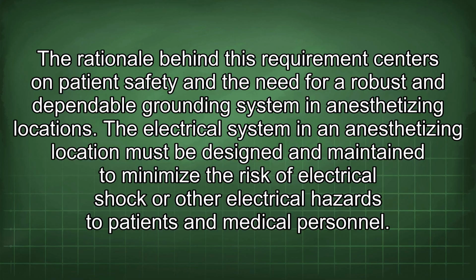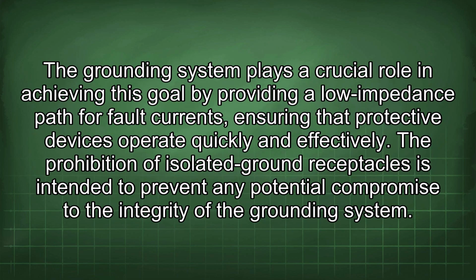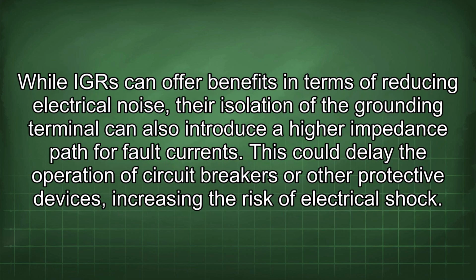The electrical system in an anesthetizing location must be designed and maintained to minimize the risk of electrical shock or other electrical hazards to patients and medical personnel. The grounding system plays a crucial role in achieving this goal by providing a low impedance path for fault currents, ensuring that protective devices operate quickly and effectively. The prohibition of isolated ground receptacles is intended to prevent any potential compromise to the integrity of the grounding system. While IGR can offer benefits in terms of reducing electrical noise, their isolation of the grounding terminal can also introduce a higher impedance path for fault currents.